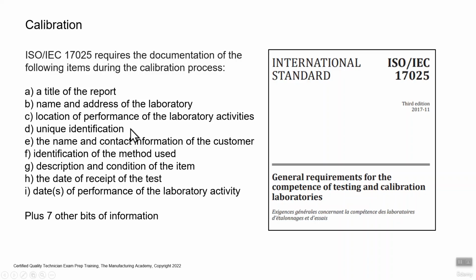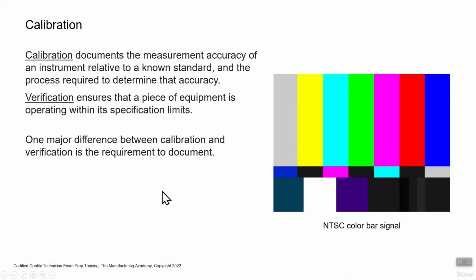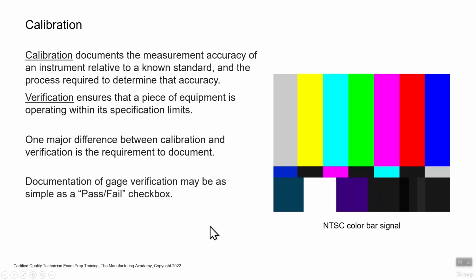So again, the difference between calibration and verification, well, look at all this stuff. I mean, you're recording all sorts of environmental conditions and the serial number of the standard you used to calibrate the device and all sorts of other things. Verification, you don't have any of those requirements. So, and again, one major difference, we said that already, is the requirement to document. Documentation of gauge verification could be as simple as a checkbox. Yes, no, pass, fail. And again, they serve different purposes. Verification is not calibration, but it's very important to maintain the accuracy of your instruments.